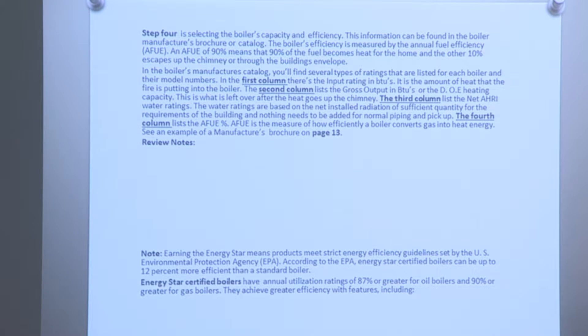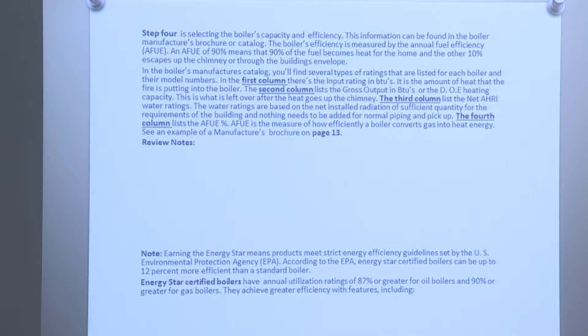Step 4 is selection of boiler capacity and efficiency. This information can be found in the boiler manufacturer's brochure or catalog. The boiler's efficiency is measured by the Annual Fuel Utilization Efficiency, AFUE. An AFUE of 90 means 90% of the fuel becomes heat for the home and the other 10% escapes through the chimney or building envelope. In the manufacturer's catalog, you'll find several ratings: the input rating in BTUs (heat put into the boiler), the gross output in BTUs or DOE heating capacity (what's left after heat goes up the chimney), the net AHRI water ratings, and the AFUE percentage.